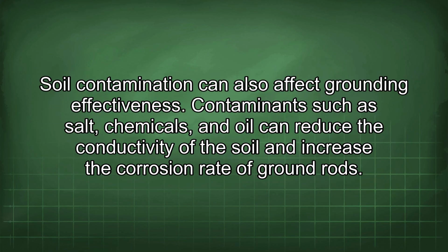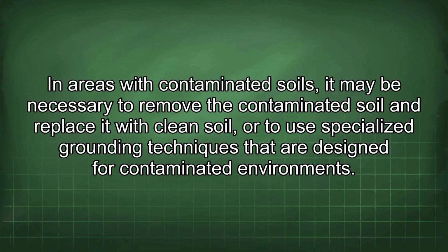Soil contamination can also affect grounding effectiveness. Contaminants such as salt, chemicals, and oil can reduce the conductivity of the soil and increase the corrosion rate of ground rods. In areas with contaminated soils, it may be necessary to remove the contaminated soil and replace it with clean soil, or to use specialized grounding techniques that are designed for contaminated environments.